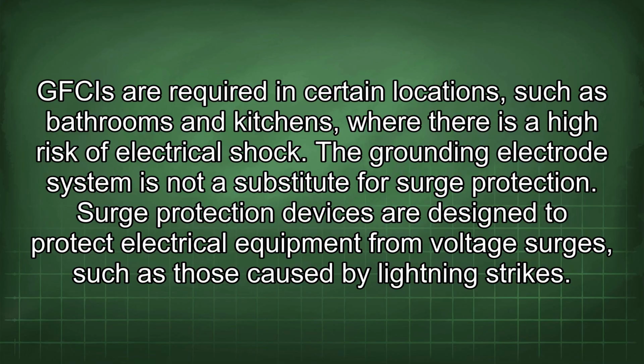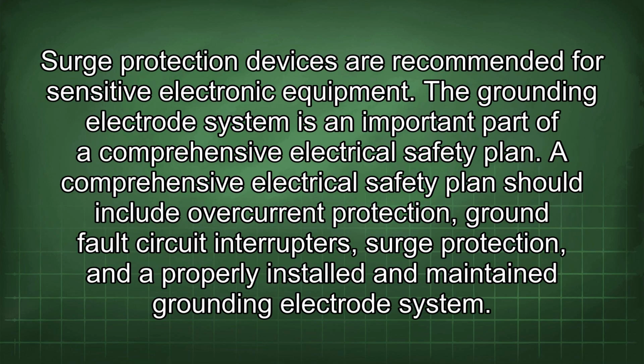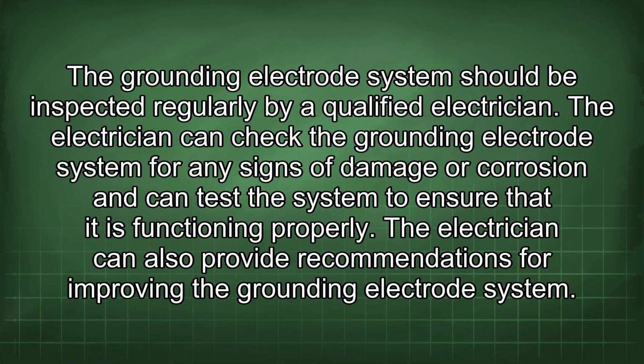The grounding electrode system is not a substitute for surge protection. Surge protection devices are designed to protect electrical equipment from voltage surges, such as those caused by lightning strikes. Surge protection devices are recommended for sensitive electronic equipment. The grounding electrode system is an important part of a comprehensive electrical safety plan. A comprehensive electrical safety plan should include overcurrent protection, ground fault circuit interrupters, surge protection, and a properly installed and maintained grounding electrode system. The grounding electrode system should be inspected regularly by a qualified electrician. The electrician can check the grounding electrode system for any signs of damage or corrosion and can test the system to ensure that it is functioning properly.